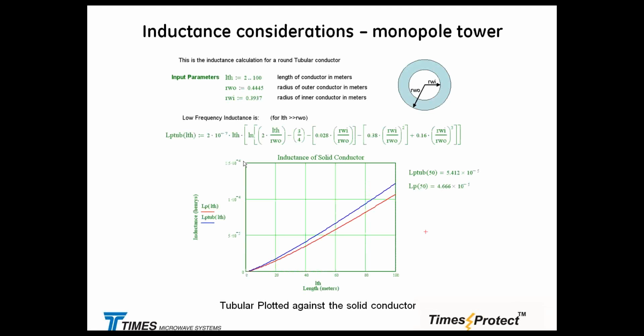There are various ways of calculating inductance. Inductance is treated as an electrical value, but it is purely the geometry of the conductor we are talking about. Typically, with a three-legged or four-legged tower, we are going to have some mutual inductance working against us. But in the monopole situation, you can assume anywhere from 0.6 to 0.8 microhenry per meter, which is 0.6 to 0.8 every 3 feet or so. And it is going to be linear by nature.